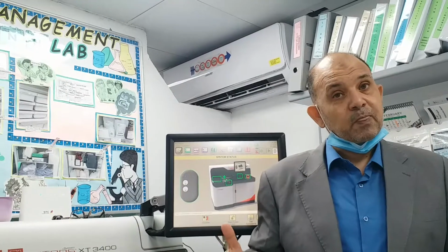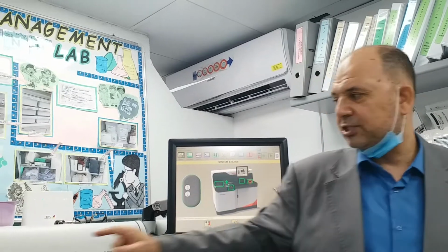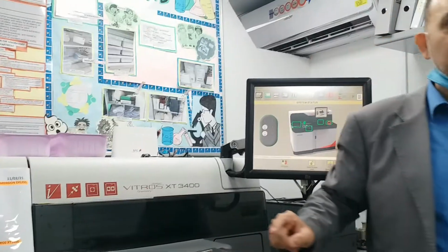After some time, each result you process is checked by IntelliCheck. It checks whether the result is within the mean and median stored before. If it's okay, it passes without any problem.